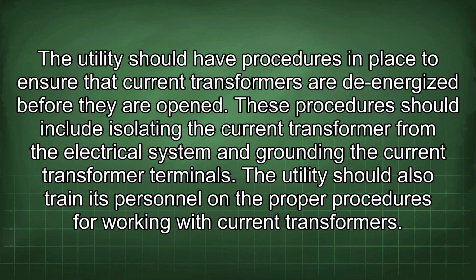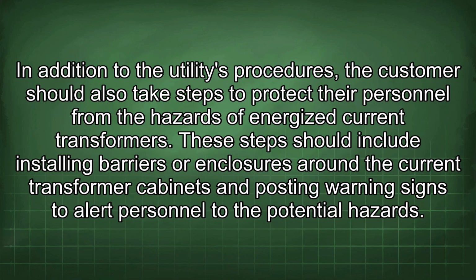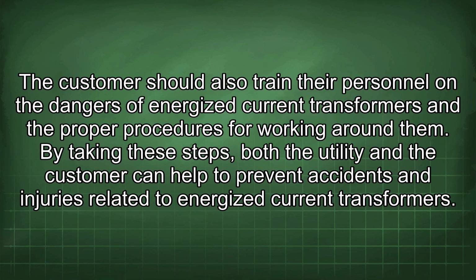The utility should have procedures in place to ensure that current transformers are de-energized before they are opened. These procedures should include isolating the current transformer from the electrical system and grounding the current transformer terminals. The utility should also train its personnel on the proper procedures for working with current transformers. In addition to the utility's procedures, the customer should also take steps to protect their personnel from the hazards of energized current transformers. These steps should include installing barriers or enclosures around the current transformer cabinets and posting warning signs to alert personnel to the potential hazards. The customer should also train their personnel on the dangers of energized current transformers and the proper procedures for working around them.